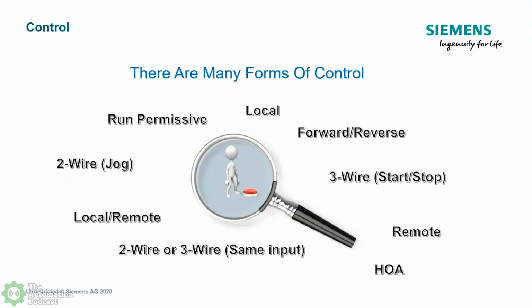Well, it can do all types of stuff. It can do run permissives. It can do local control, forward and reverse, 2-wire, 3-wire, local and remote. For our application today, local means that you're standing near the motor, and remote means that you're in some type of control room looking at 4 or 5 screens controlling a big plant, and you need to have all the information you can from that pump or that fan or that conveyor belt.